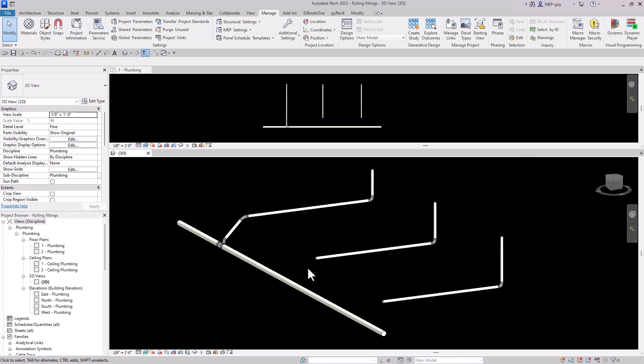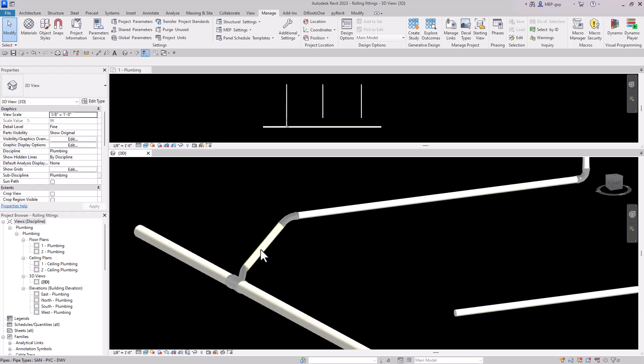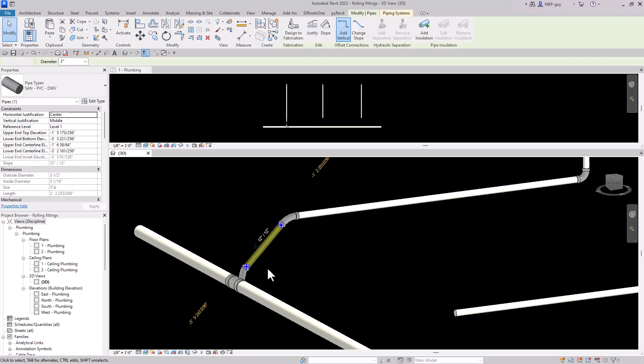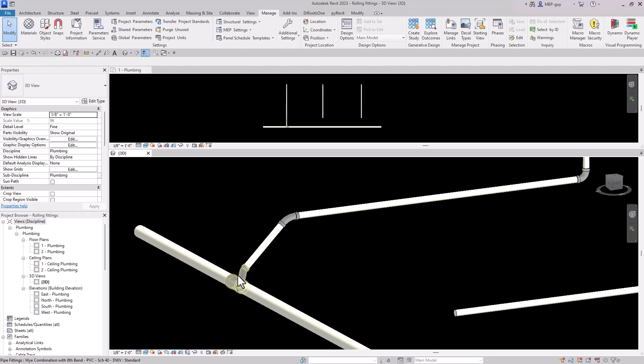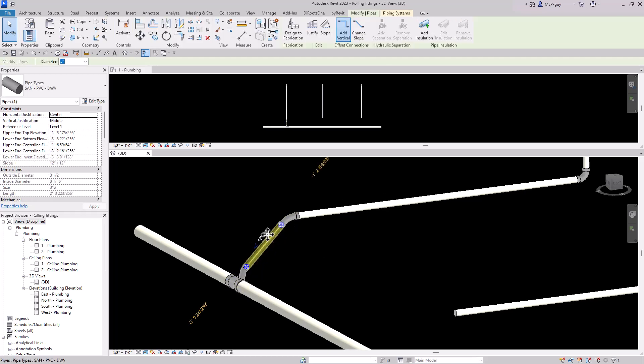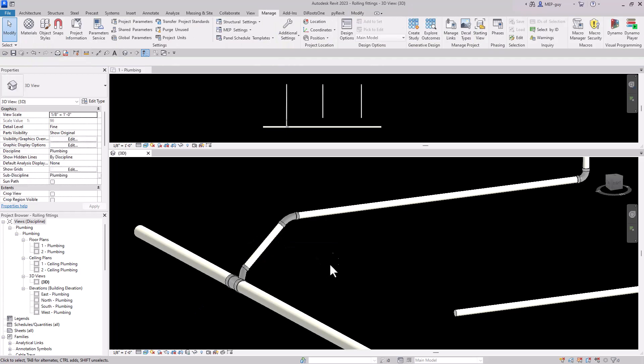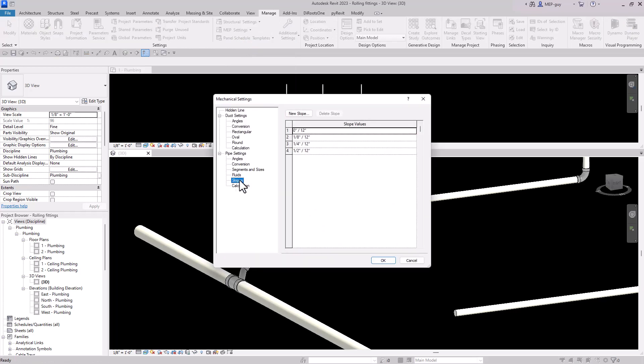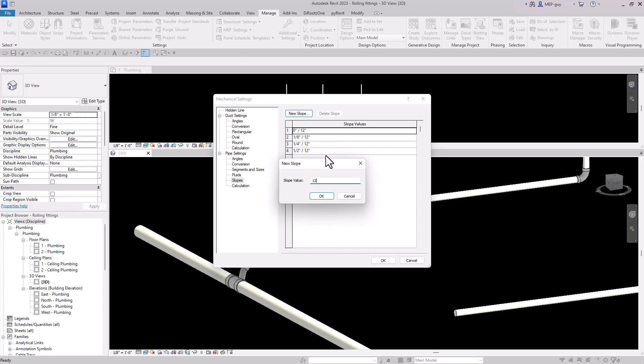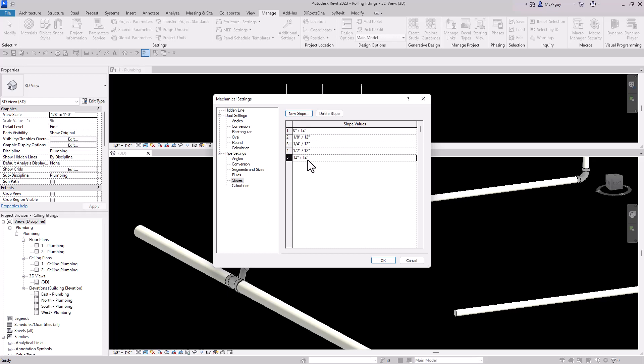For the next example, I'll show a different method — going from the main up to a pipe using a technique based on slope. A 45 degree angle is actually a slope of 12 inches per 12 inches, or one to one. So let's add that slope. Go to Manage > MEP Settings > Mechanical Settings > Pipe Settings under Slopes, click to add a new slope, enter 12 inches per 12 inches, and hit OK. Now we have this new one-to-one slope.